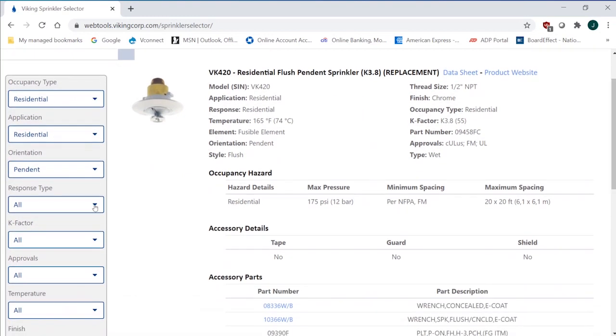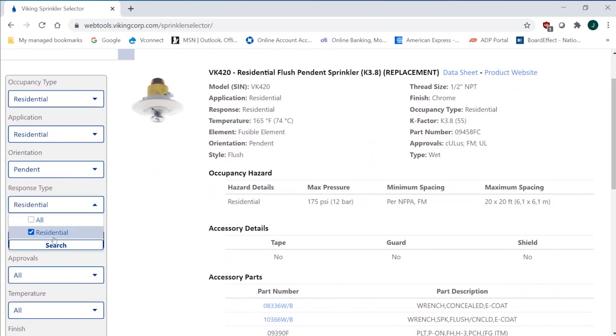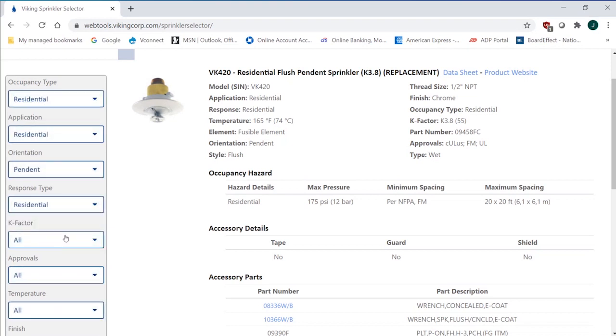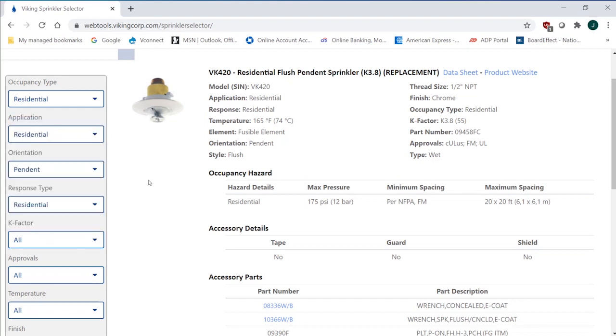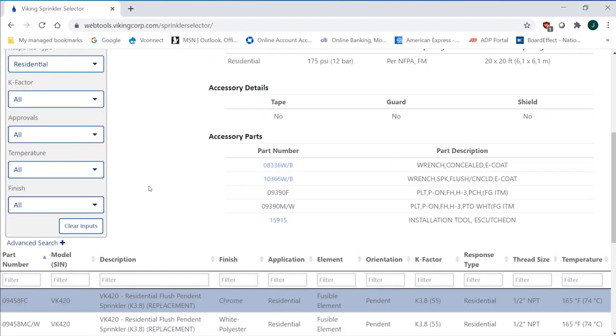Response type, obviously, is going to be quick, so there should only be one response type. We call it residential because residential technically doesn't have a category of response type, although it does use a fast response element. K-factor, now, I'm probably getting a little bit too much detail here before I have selection, so there's multiple K-factors that are available. I may not know that right now, so I may not want to narrow that down.